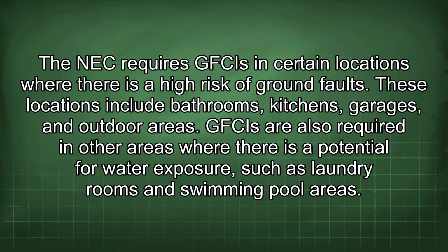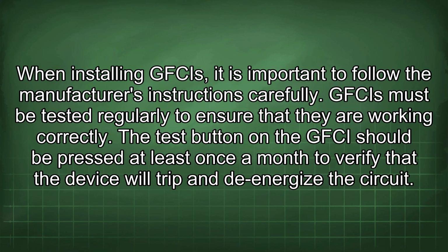The NEC requires GFCIs in certain locations where there is a high risk of ground faults. These locations include bathrooms, kitchens, garages, and outdoor areas. GFCIs are also required in other areas where there is a potential for water exposure, such as laundry rooms and swimming pool areas. When installing GFCIs, it is important to follow the manufacturer's instructions carefully.